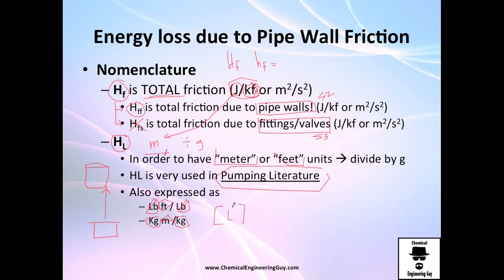Whatever I tell you, if I give you I have friction loss of five meters, you should know that if you multiply it by gravity, you will get the joules per kilogram you're losing. And backwards, if I tell you I'm losing ten joules per kilogram divided by gravity, that's about one meter of length.